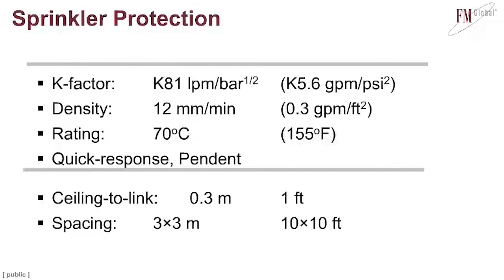Basically trying to set what the code is looking at with that 0.3 density. If you walk into a building and you see an energy storage system and you know there's a 0.3 density, what level of protection are you actually being afforded there? And if that level of protection isn't sufficient, how can you adjust the deployment of the energy storage system so that that protection is actually going to be adequate?